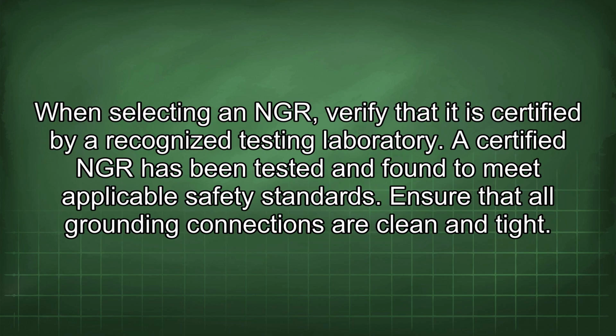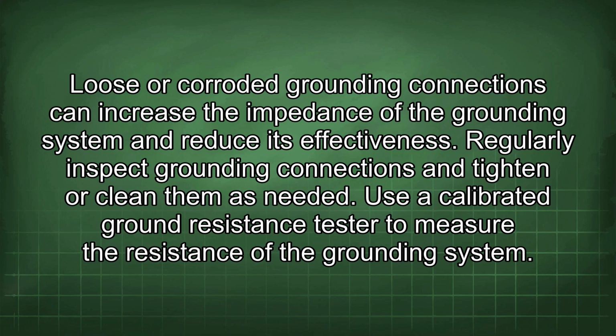When selecting an NGR, verify that it is certified by a recognized testing laboratory. A certified NGR has been tested and found to meet applicable safety standards. Ensure that all grounding connections are clean and tight. Loose or corroded grounding connections can increase the impedance of the grounding system and reduce its effectiveness. Regularly inspect grounding connections and tighten or clean them as needed.